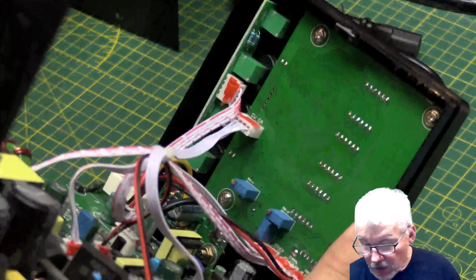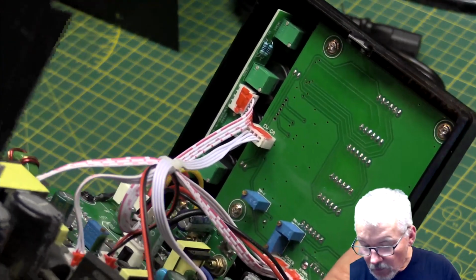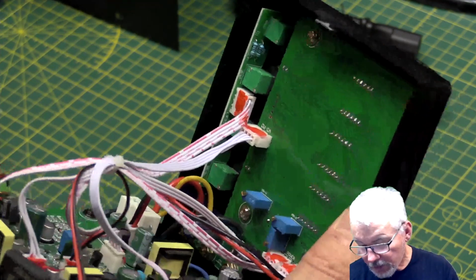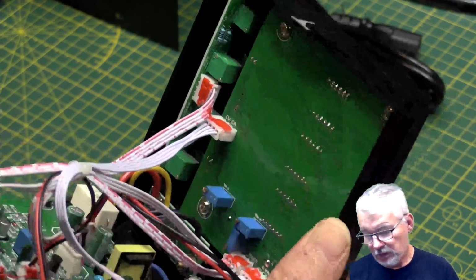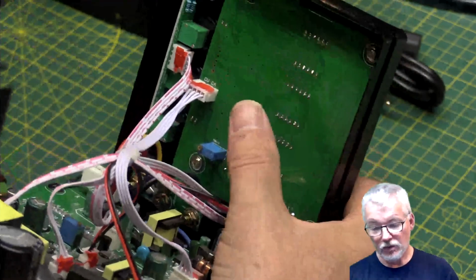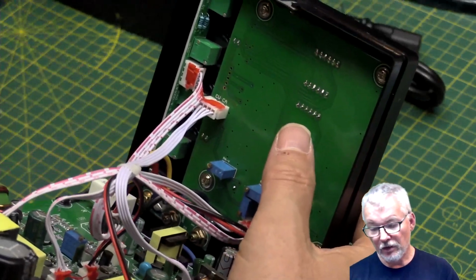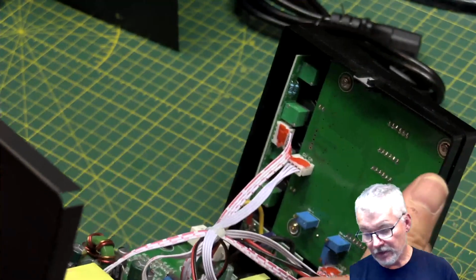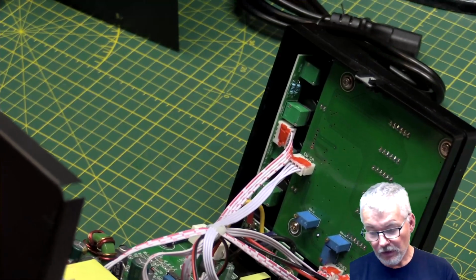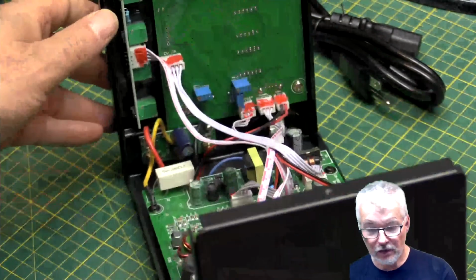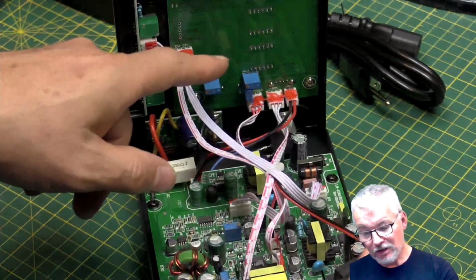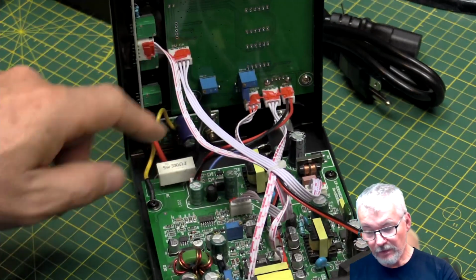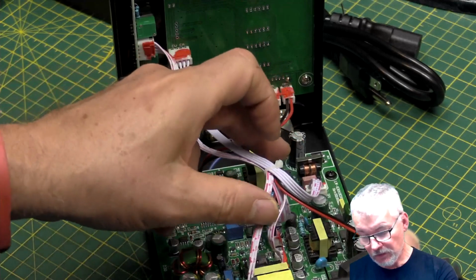But the current may be the one that needs adjusting. This is for sensing as opposed to control. Control, really, you don't care too much about whether it's accurate enough because you use the sense measurement to actually determine the voltage. Now, the one thing I am noticing here is that it's not really measuring the voltage at the output terminal.